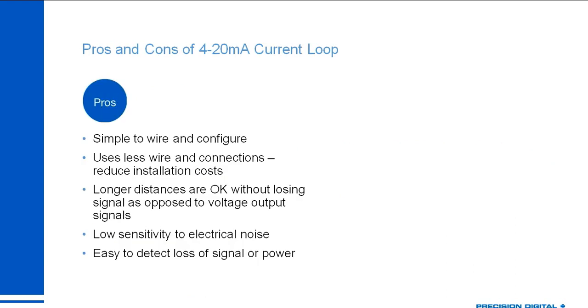Now that we understand what makes up the 4-20 loop, let's talk about why people choose to use it. The number one reason is that it's simple to wire and configure. Because you're just making one big loop with your wires, all devices only have two pins — a plus and a minus. If you have a problem or want to trace how the circuit works, you just walk your wires around the loop making sure everything's connected. It also uses fewer wires and connections than other options, such as a five-wire RS-485 Modbus device with complicated serial bus wiring.